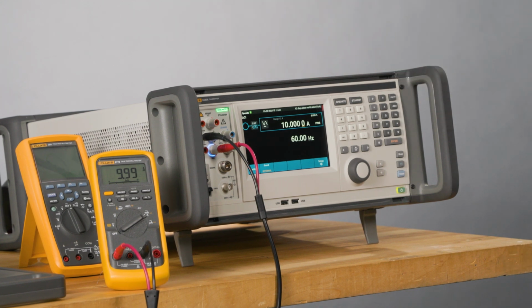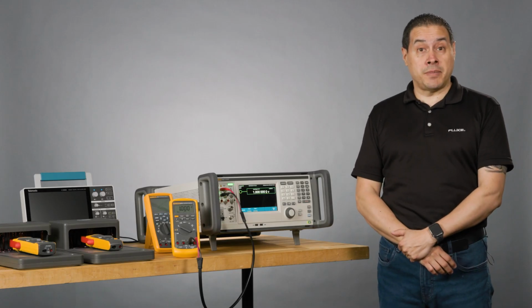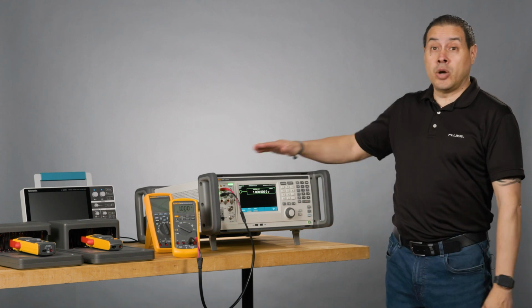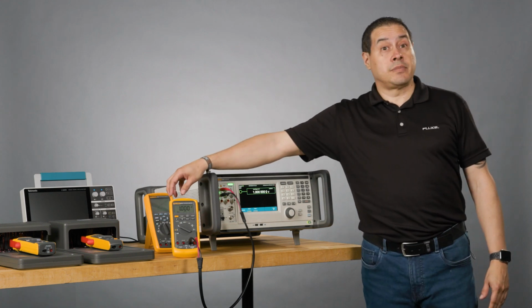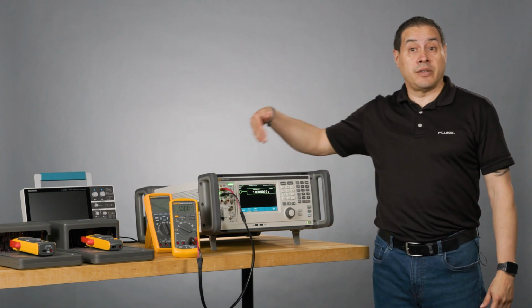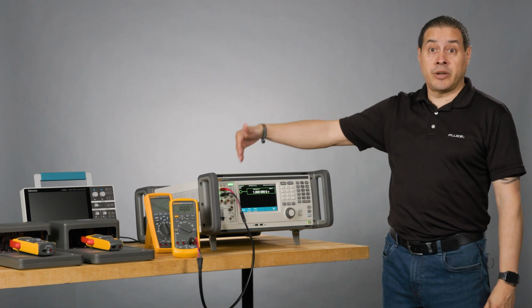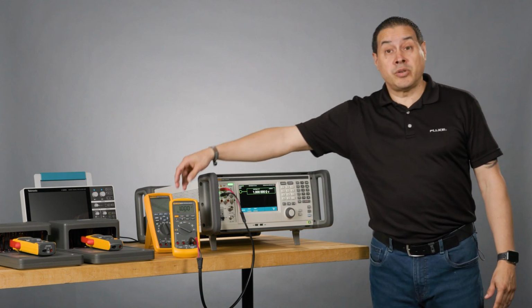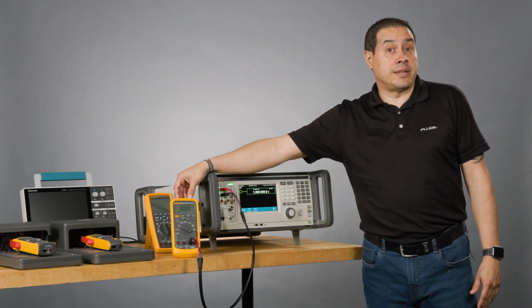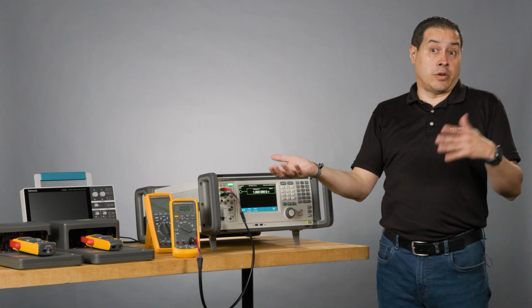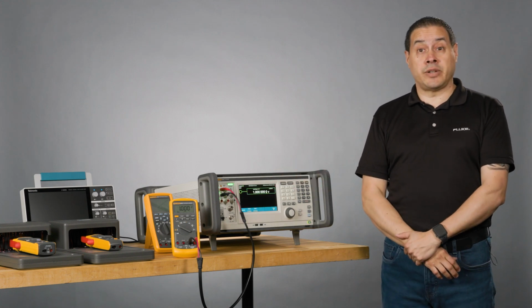And I'm done. So the purpose of calibrating a DMM is basically comparing a known source with my unit under test to check if I have an error, how much the error is, and how my unit is performing in the field. That's basically comparing a known value with an unknown value, and that's what calibration is.